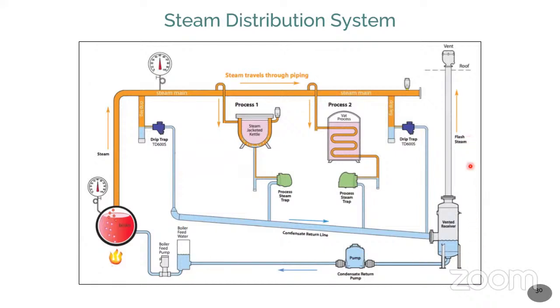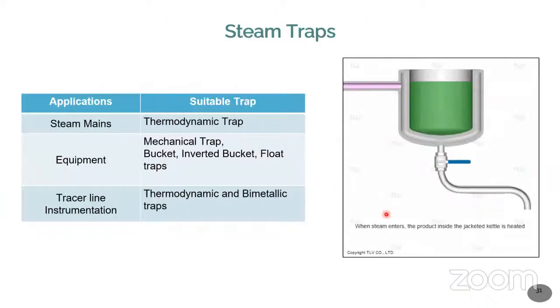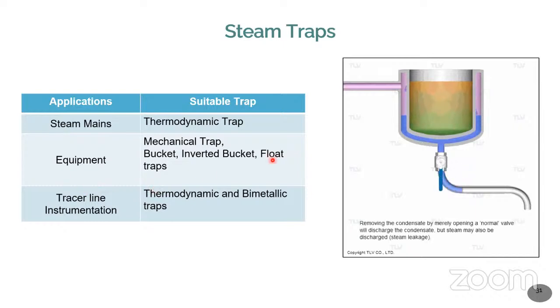Sometimes you can have flash steam also, but that is not required for this event. So you have steam traps also available. Steam traps, as I told you, collect the water in the system. We have different types of steam traps available. You have thermodynamic steam traps, bimetallic traps, float type, as I told you in the previous picture, and similarly mechanical traps, bucket type traps.